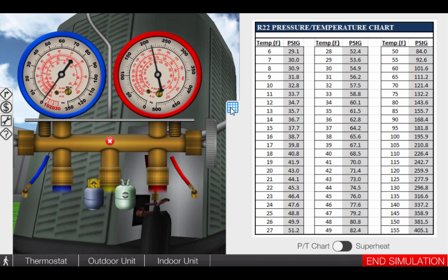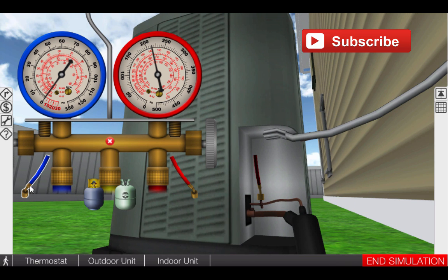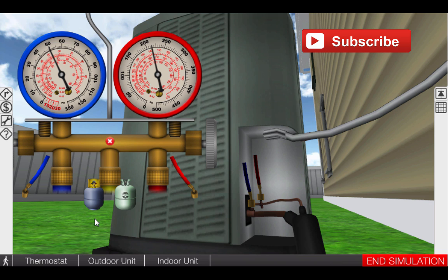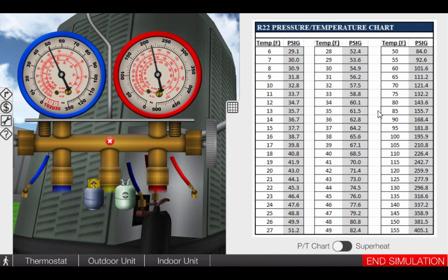We're going to store the chart away and place the blue hose on the suction line connection on the low side of the system. Here we can see we have 50 PSIG of suction pressure. Going back to the temperature pressure chart, 50 PSI of suction pressure corresponds to only a 26 degree evaporator temperature.